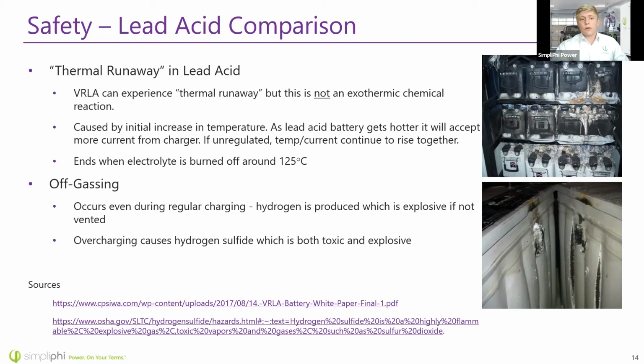The resistance of the battery will decrease and it will accept more charge current. That extra charge current heats up the battery more, and the cycle just continues. Ultimately this ends when the electrolyte is burned off around 125 degrees Celsius, not too far above the boiling temperature of water. So nothing crazy, but the danger is that gas is released during this process.